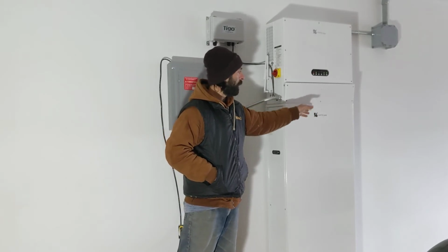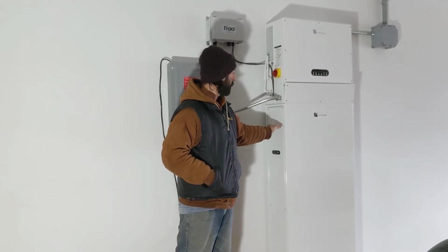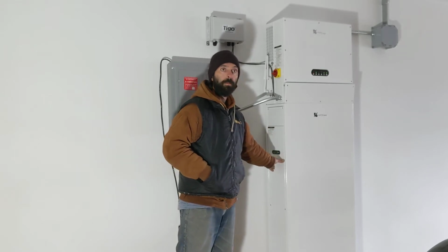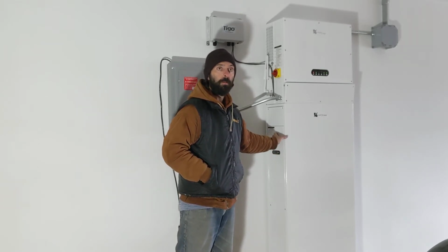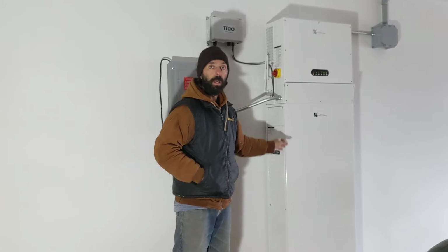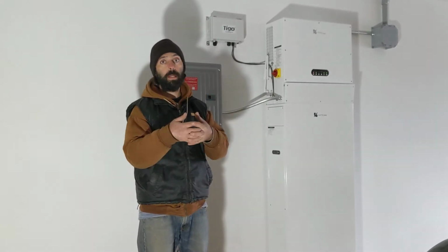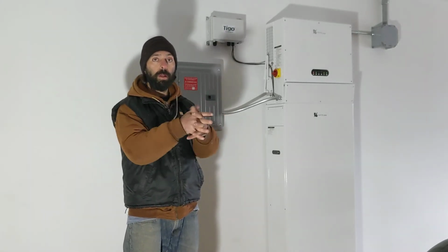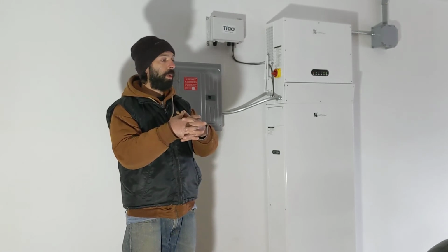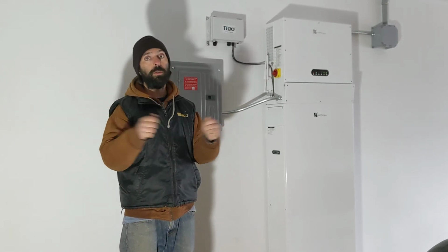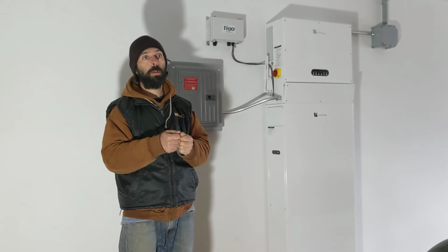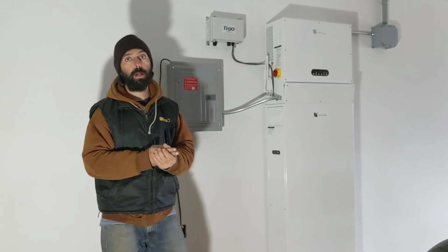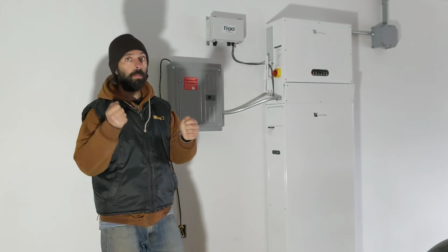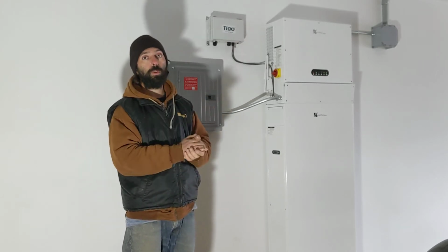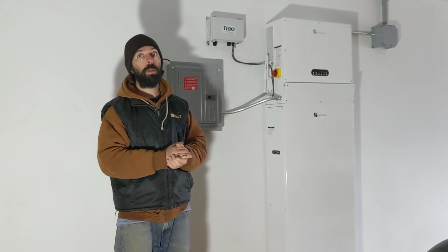They slide from the side of the cabinet and plug into the back plugs, and you don't need to wire anything. It's a plug-in connector. You just slide the battery in and it plugs into the connector, so there's no need to do wiring, no need to measure wires, cut wires, put plugs, or anything like that. You just slide the battery module in, secure it with 4 provided screws, and it's over. It's a one-man job.